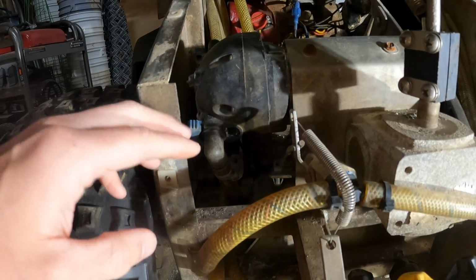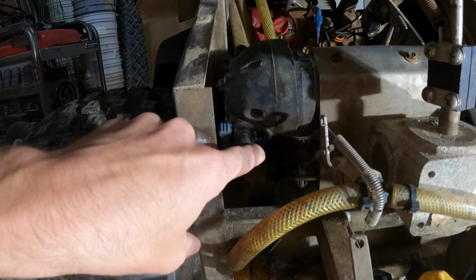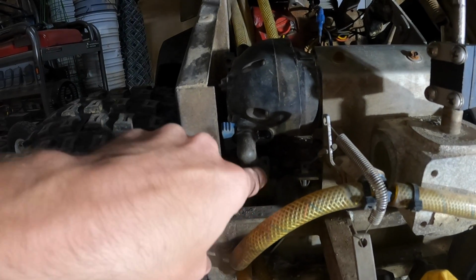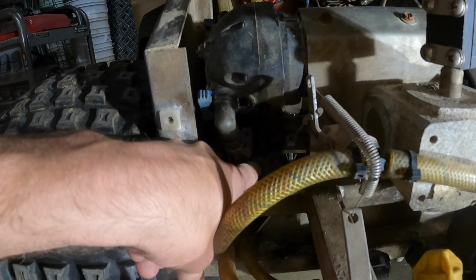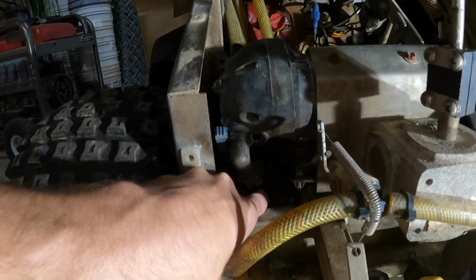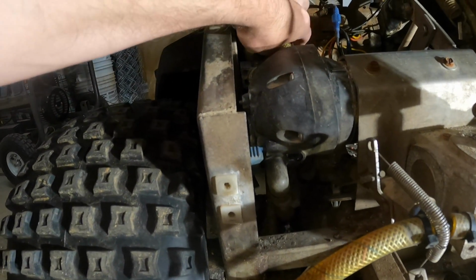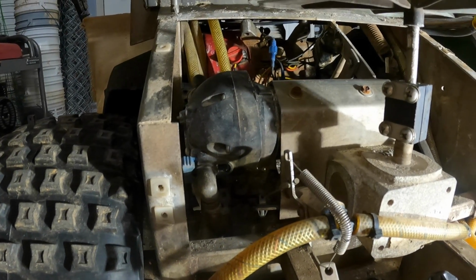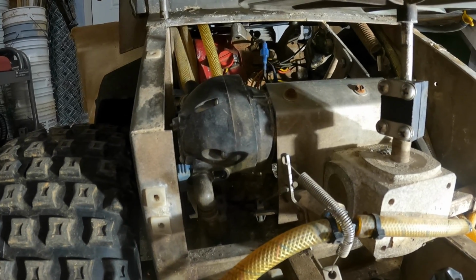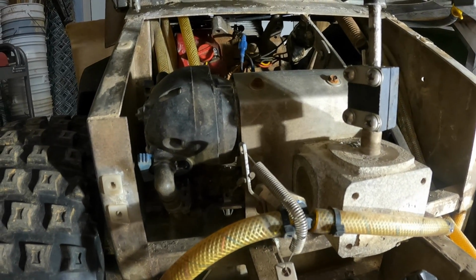So we're going to try to reroute some of these lines here. This is your suction side. We're going to try to reroute that to where it's a little bit less of a loop down in here, and maybe we won't have as much air buildup coming from the tank. Even if you're not having these problems, this would be a good video on how to remove the pump and reinstall the pump, and I'm also going to show you how to clean the pump.